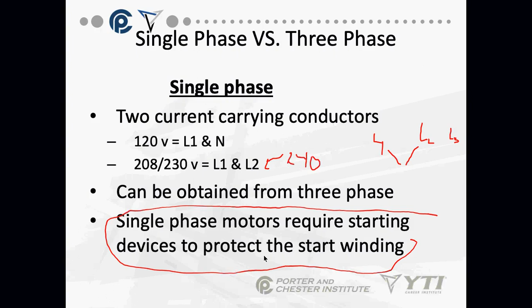This is the most important point from what we're dealing with in HVAC. Single-phase motors require a starting device. Okay, it's not only to protect the start winding, but it's also to provide that additional out of phase for the start winding. Okay, requires starting devices.